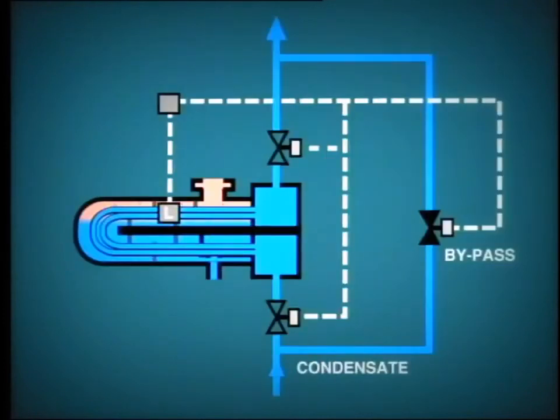In some installations, the high water level causes the condensate to bypass the heater altogether by automatically operating the motor actuated isolating valves in the following sequence. Open bypass valve and then close inlet and outlet valves.